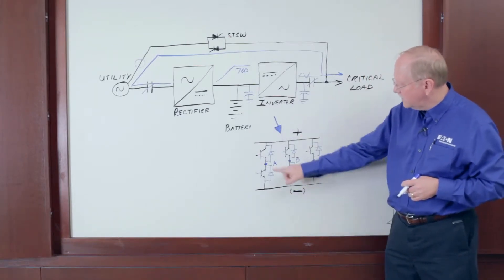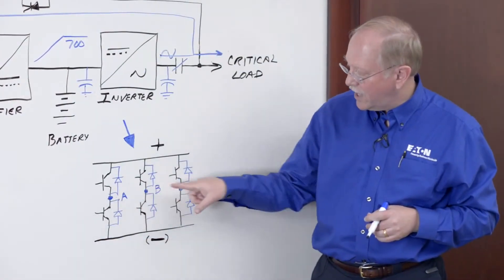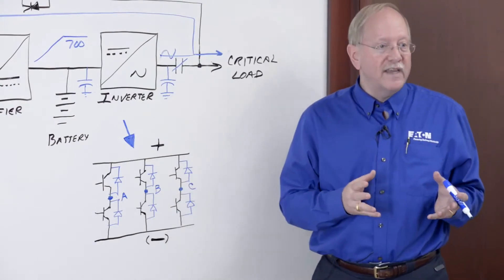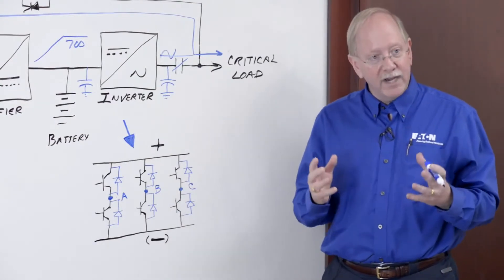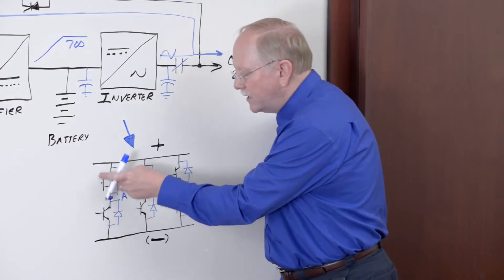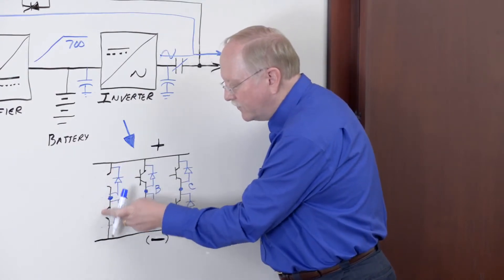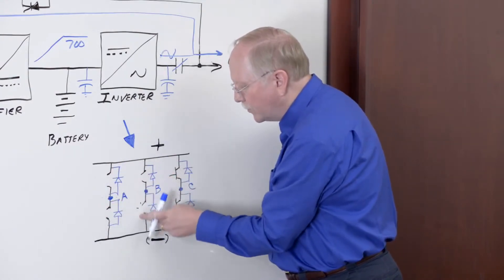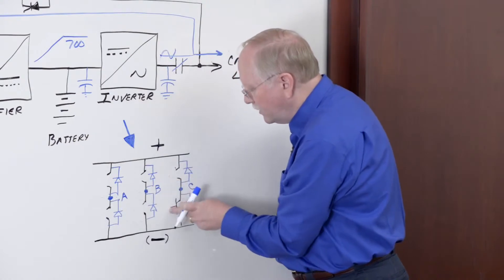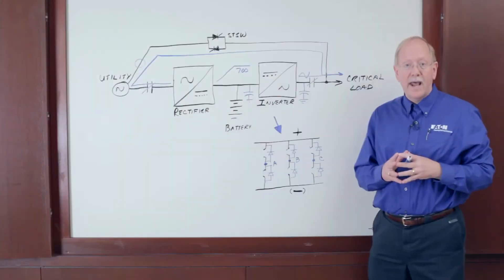Here's positive and negative DC, and the inverter transistors create phase A, B, and C, a three phase AC output. But if I'm not gating those transistors when I'm suspended, the transistors disappear from the circuit. They're open switches, leaving me with six diodes in a bridge rectifier schematic.